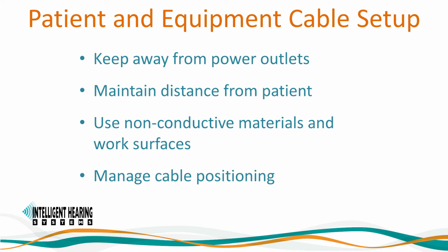The bed, chair, or car seat framing may have metal components that will act as an antenna and pick up unwanted EMI. It is important to isolate the patient and equipment from these metal surfaces. Lastly, manage cable positioning. Do not cross electrode leads over transducers, USB cable, and/or power cables. Cables must not cross each other. Run electrode cable and leads from one direction to the patient and earphone cable from the other direction to the patient. Typically, insert earphones will come from behind the patient's head, and the insert earphone speaker boxes will be clipped to the pillow and beside the patient's ears.